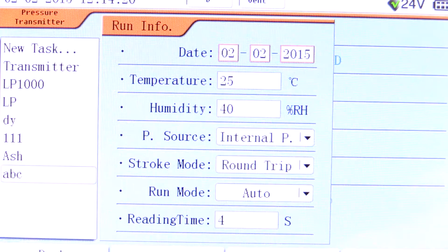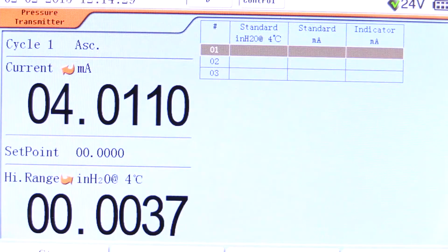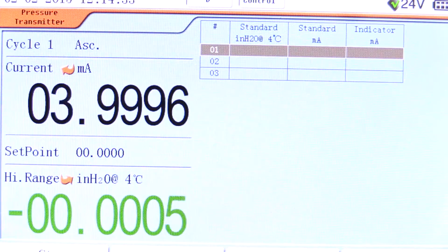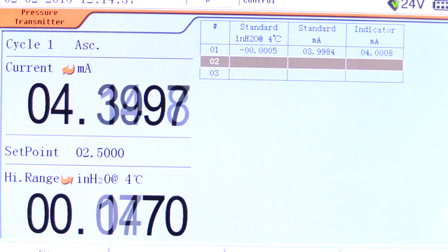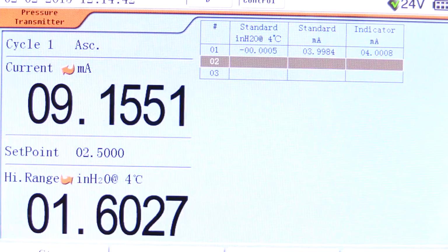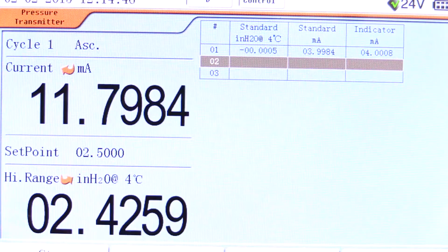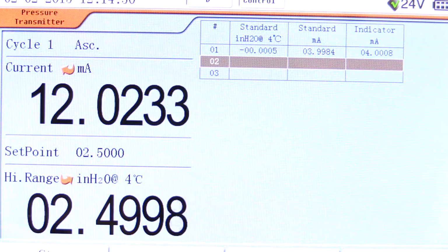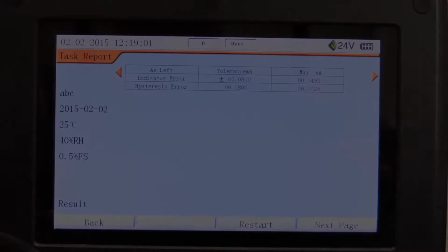After recording the environmental conditions, the task will begin to run automatically. Pressures are generated, and when the defined wait time is reached after stability, the transmitter's analog output is measured and recorded on the table on the right. Manual entries can also be performed if desired.